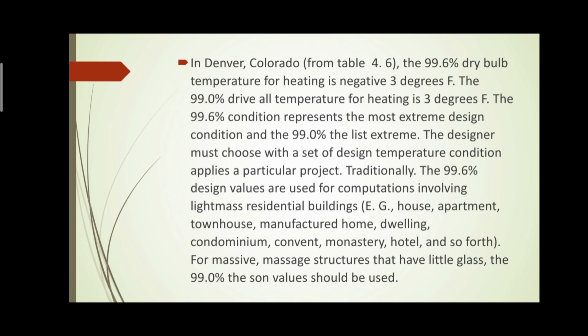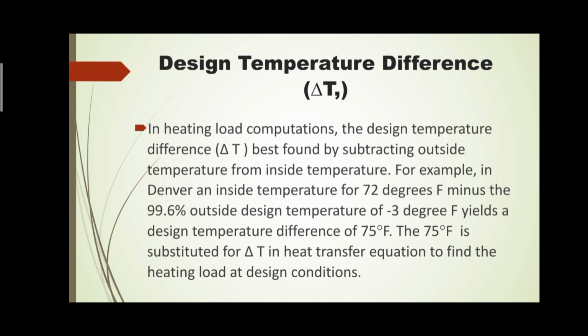In Denver, Colorado, the 99.6% dry bulb temperature for heating is negative 3° Fahrenheit. The 99.0% dry bulb temperature for heating is 3° Fahrenheit. The 99.6% condition represents the most extreme design condition and the 99.0% the least extreme. The designer must choose which set of design temperature conditions applies to a particular project. Traditionally, the 99.6% design values are used for computation involving light mass residential buildings, for example, house, apartment, townhouse, manufactured home, dwelling, condominium, convent, monastery, hotel, and so forth. For massive structures that have little glass, the 99.0% value should be used.